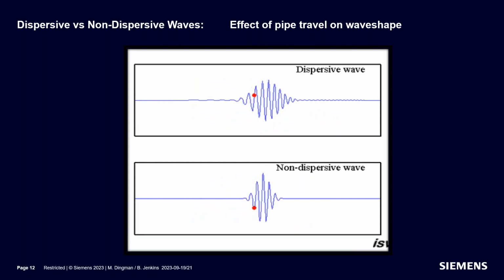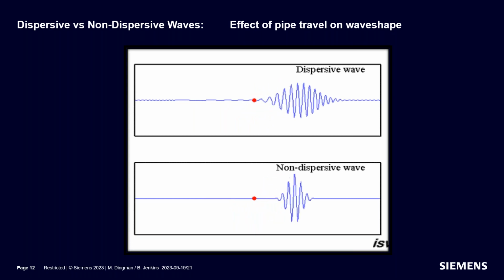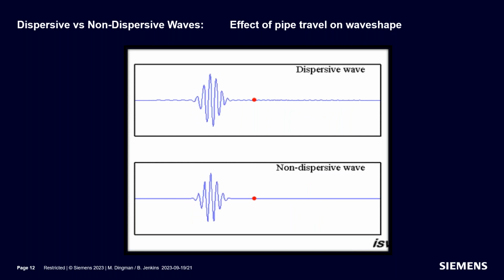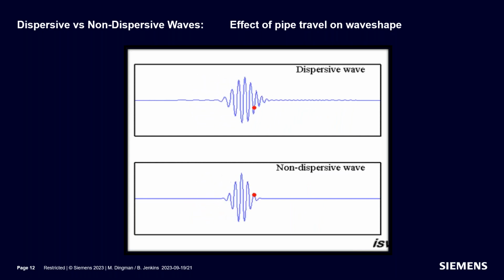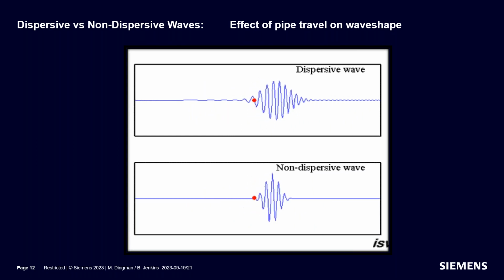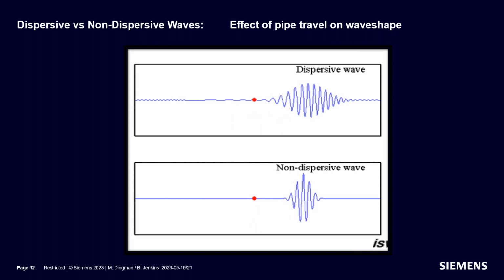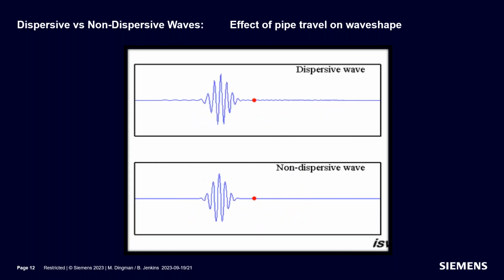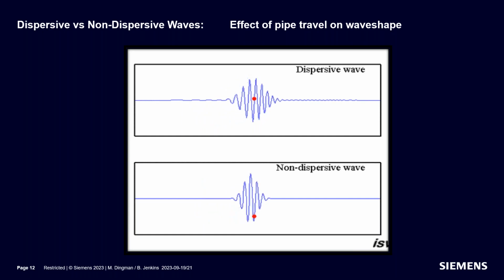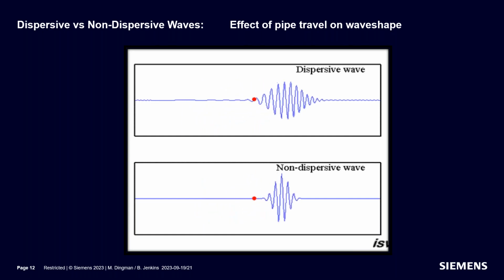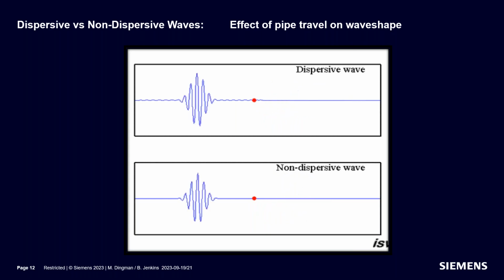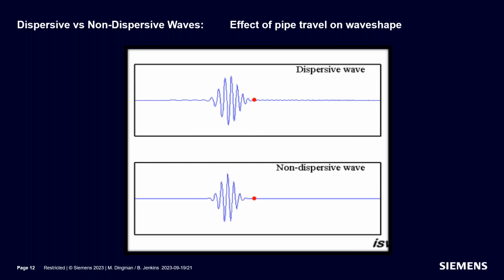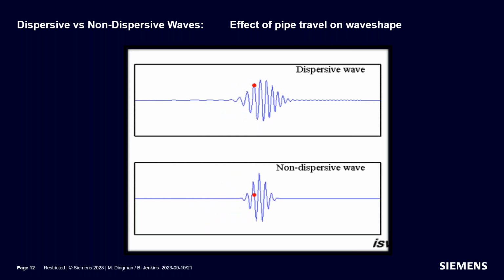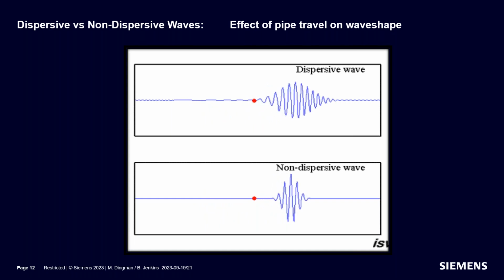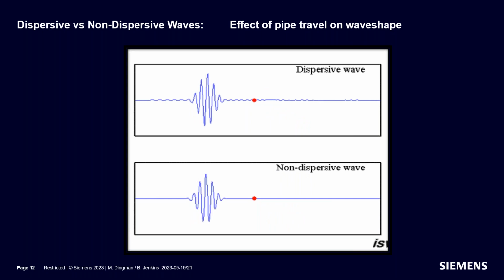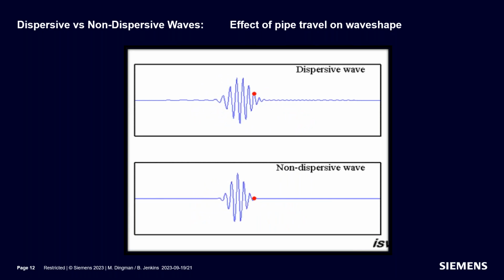So think about what I showed you earlier with Snell's law, with the refraction angle of the sonic beam relative to the fluid. If you have your transducers on the pipe and your fluid changes, that means your refraction angle changes. That means the position of where the signal is arriving at the received transducer has changed. And if you have a dispersive wave, that means that wave shape is now changing, but it's changing in one direction versus the other direction. And when those two don't match up, you get shifts in calibration, shifts in your flow reading. So that's what's so critical about the Lamb wave technology, and why others waited for the patents to run out so they could utilize that technique.